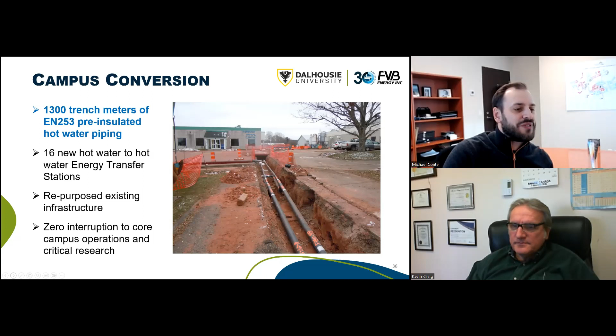To highlight some of what we had to do on campus, we had to run all new hot water piping. There was steam infrastructure in the ground that was over 40 years old, so we elected to go with EN 253 pre-insulated heating pipes. All in all, we ran about 1,300 trench meters over the course of 2 summers. The image shows a photo connecting one of the buildings on campus, you can see that nice red soil they have out in the Maritimes. Next slide, please.